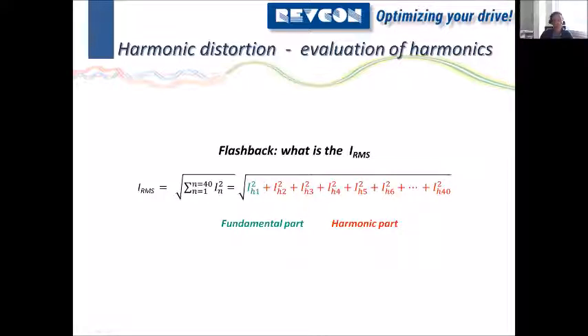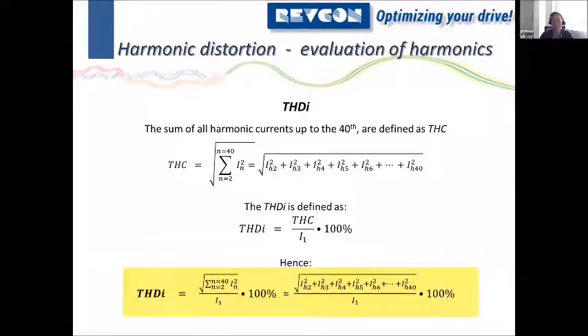When we calculate the THDI, we want to put these two parts in a relationship to give you a value that says what the quality of my input current is. That's how you could interpret this. So looking at the total harmonic current, which is basically the same as the IRMS but not including the fundamental part, we only look at the second up to the 40th or 50th harmonic. This is the harmonic part. To get the THDI, we divide this harmonic part by the fundamental, which is the first harmonic. So in the end, we have this equation where we divide the harmonic part by the fundamental part. This way we get the THDI, which is what we need to evaluate the harmonic distortion of a signal.